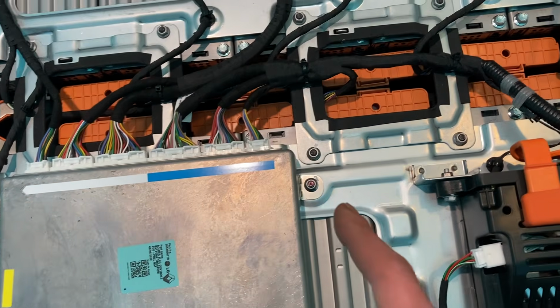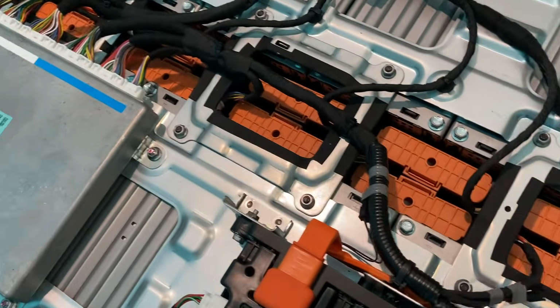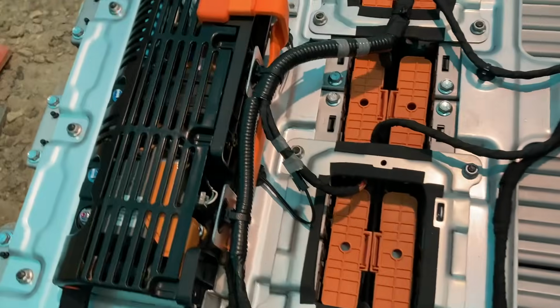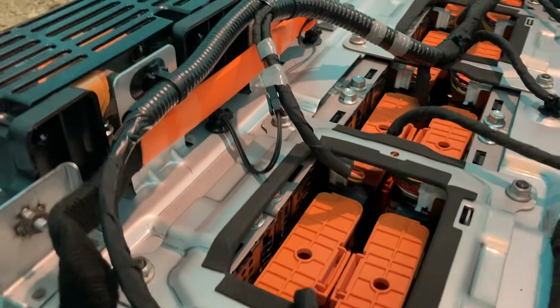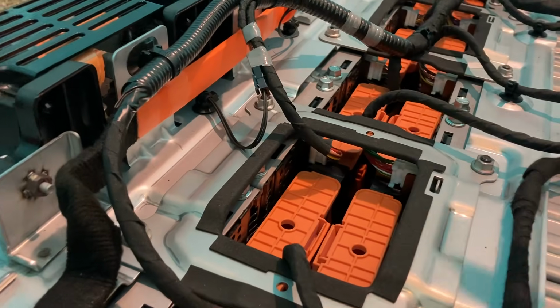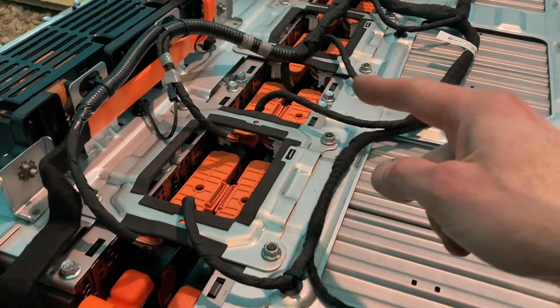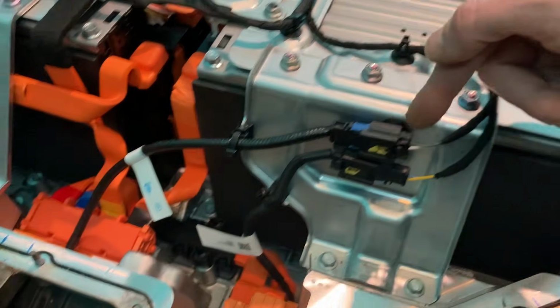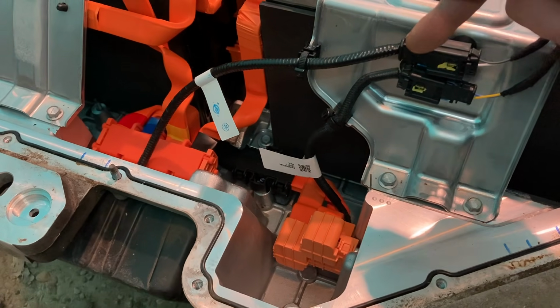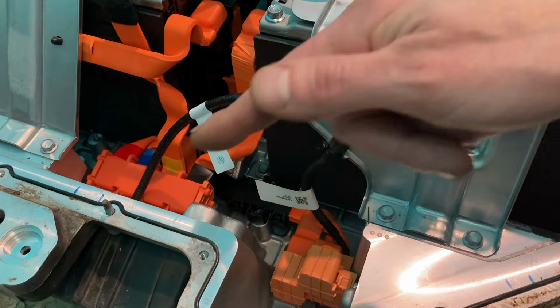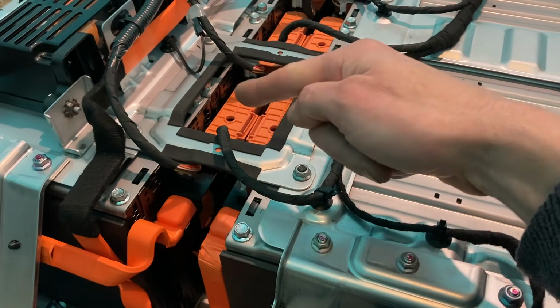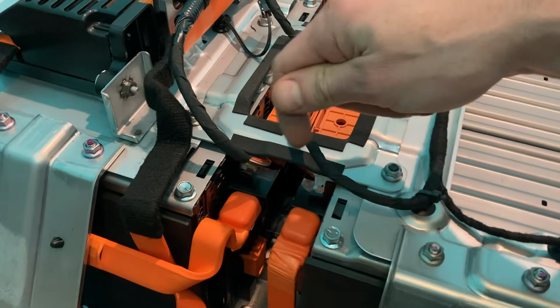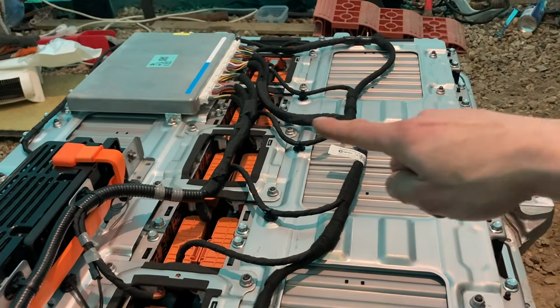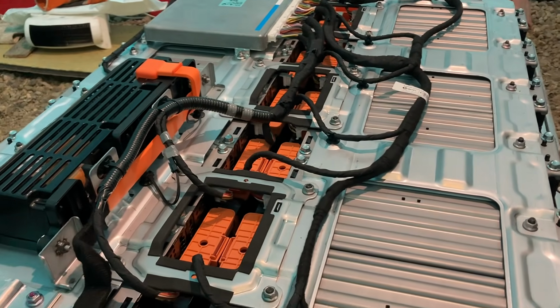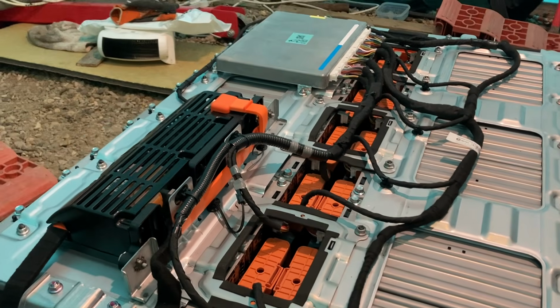So then we can kind of see, on each module if we go down here, you've got that white connector there and there, so that's our voltage monitoring. You can see that's obviously the interlock for the safety plug, and that cable there is going to here and feeding round and back to that BMS, so it can monitor all the voltages - and that's what was telling us it was low.